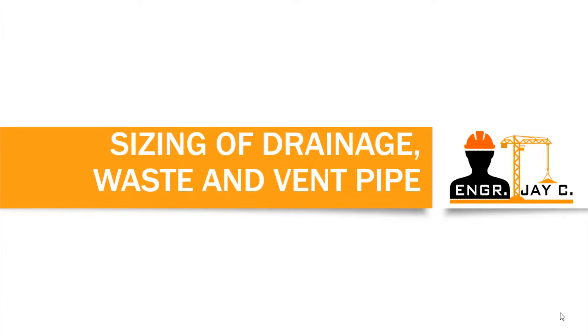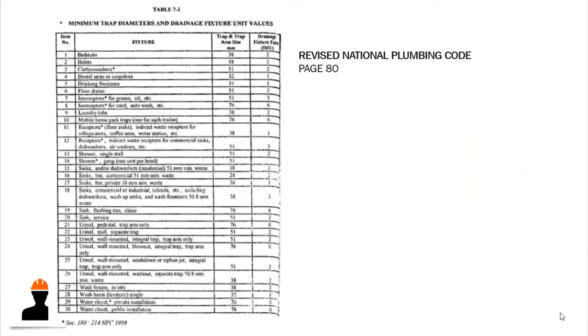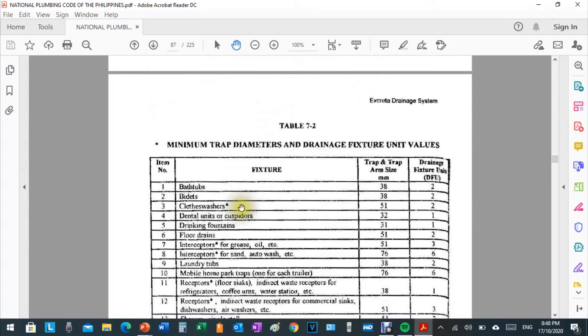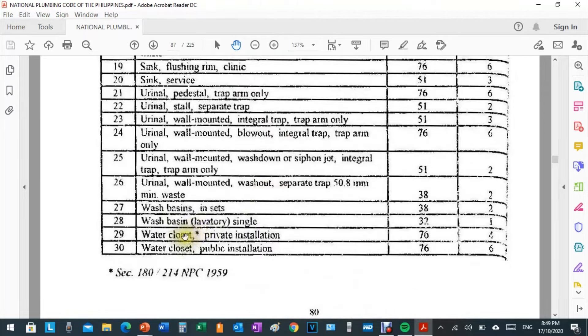In identifying the size of your pipe, the first thing you need to do is compute the total drainage fixture unit by referring to Table 7-2 of the Revised National Plumbing Code, found on page 80. This table lists fixture types, their required minimum trap arm diameter, and their equivalent drainage fixture unit. For example, bathtubs have a minimum trap arm of 38 millimeters and a drainage fixture unit of 2. Water closets for private installation require a minimum 76 millimeter trap arm.